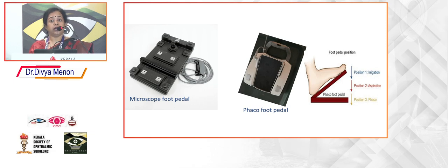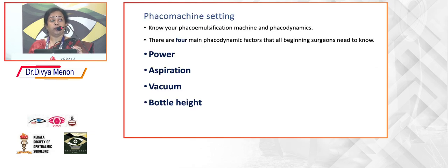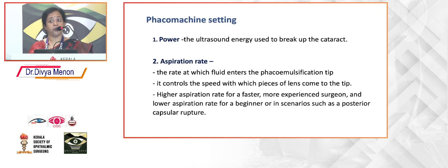The phaco foot pedal again has three positions, as you all know. Position 1 is irrigation, position 2 is aspiration, and position 3 is phaco. You must be thorough with your phaco machine settings and phaco dynamics. There are four main things: power, aspiration, vacuum, and bottle height. Power is the ultrasound energy which is used to break up the cataract. Aspiration rate is the rate at which the fluid enters the phacoemulsification tip. It controls the speed with which the pieces of lens come into the phaco tip.